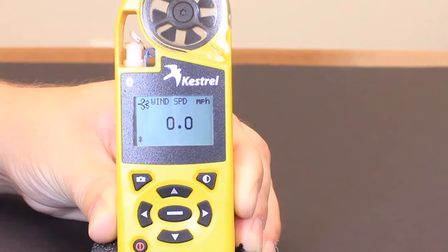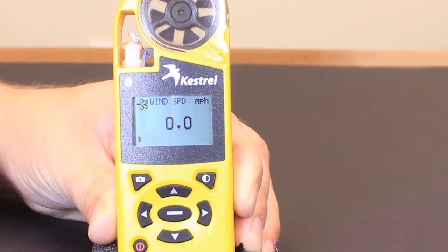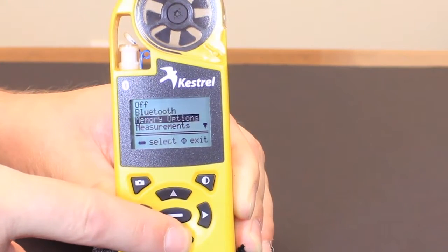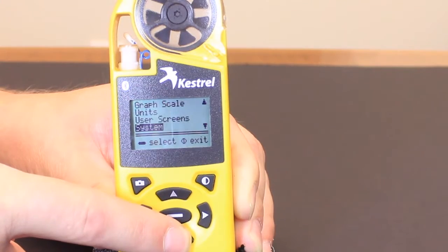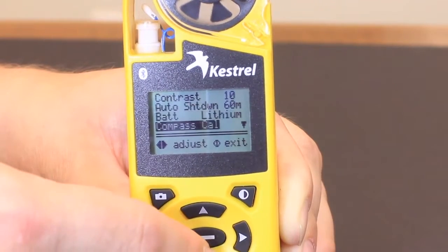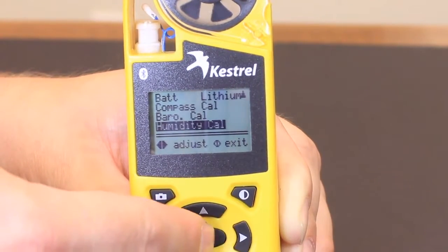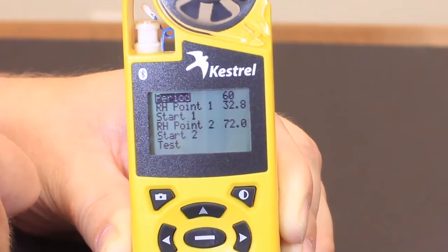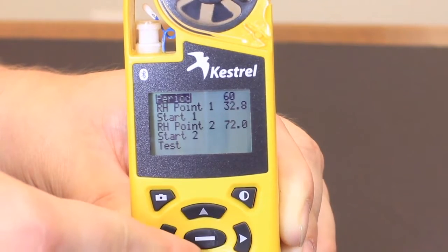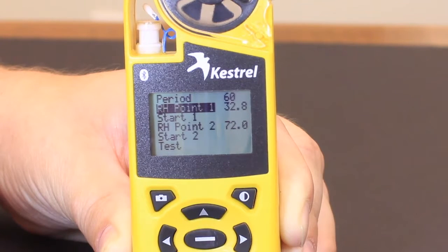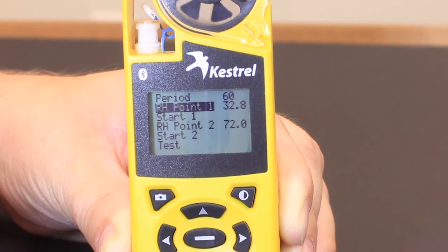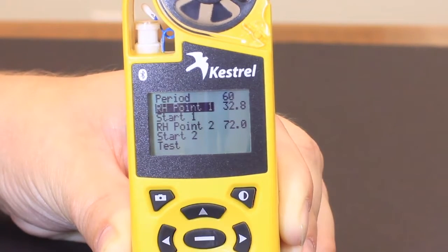In order to calibrate the humidity on the Kestrel 4000 series, you'll turn the unit on and press the power button to get to the main menu. You will scroll down until you see system. The period is going to be 60. That's going to be the amount of minutes that you want to leave it in each chamber, so do not change that. You'll go down to the RH.1, and you want to make sure that this reads the same as the first chamber, which is 32.8%, but use the left and right if it doesn't to adjust this to 32.8.